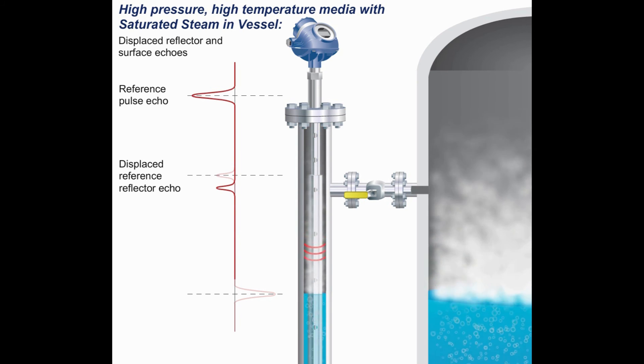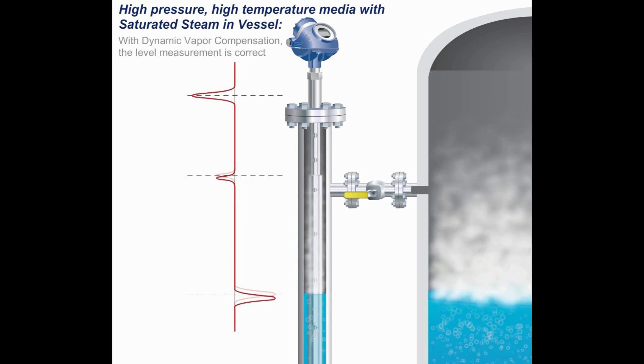Because the transmitter knows exactly where the reflector is, the distance the reflector pulse has been displaced can be used to calculate how much compensation is needed. It then determines the correct distance to the surface pulse and outputs the correct level.